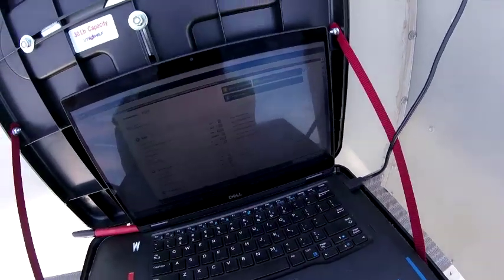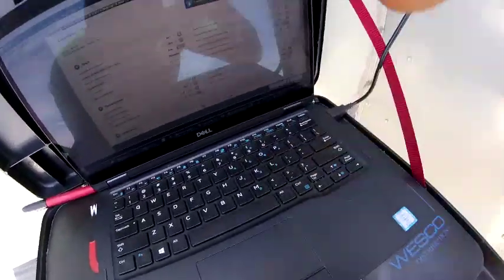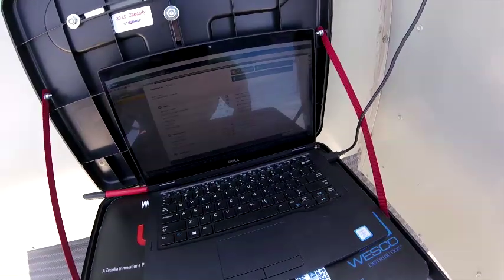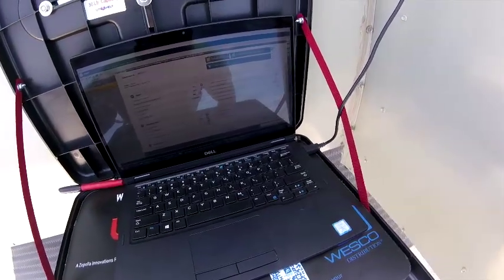Try to find out why this discharge temperature. Let's see if it starts dropping. Cooling capacity now 33%. So this should start dropping. Like I said, I can't look at the fan power box from up here. So here in a minute, I'll call the BAS team and let me know if that zone is satisfying or not.